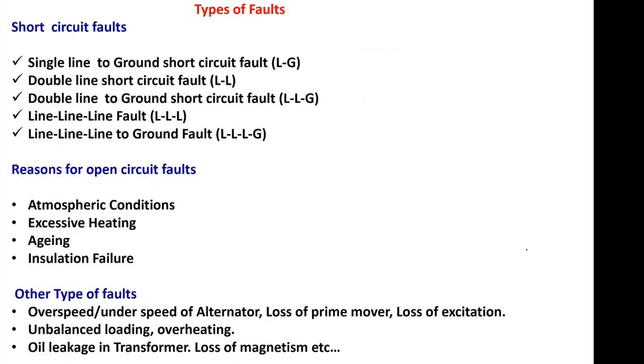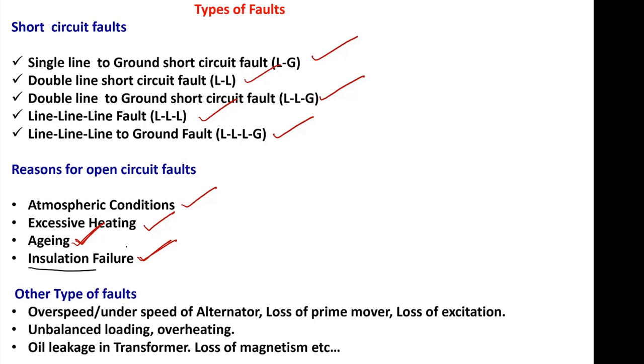Next, short circuit faults. There are five types: LG fault, LL fault, LLG fault, triple LL, and triple LLG fault. Short circuit faults occur due to atmospheric conditions, excessive heating, aging of equipment, and insulation failure. The most common reason is failure of insulation.